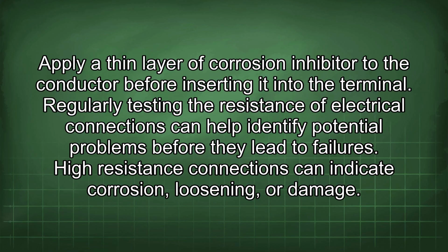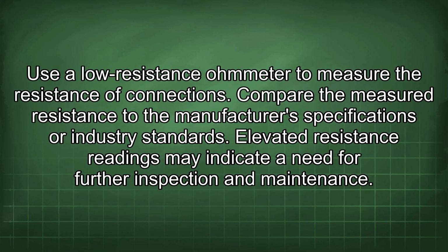Regularly testing the resistance of electrical connections can help identify potential problems before they lead to failures. High resistance connections can indicate corrosion, loosening, or damage. Use a low resistance ohmmeter to measure the resistance of connections. Compare the measured resistance to the manufacturer's specifications or industry standards. Elevated resistance readings may indicate a need for further inspection and maintenance.